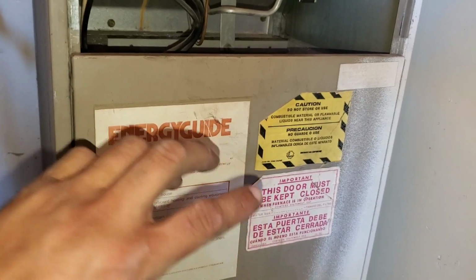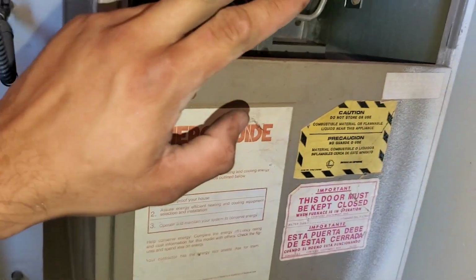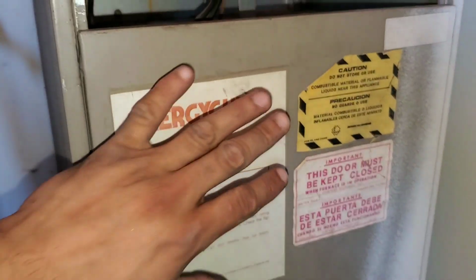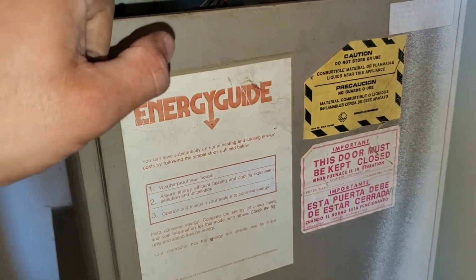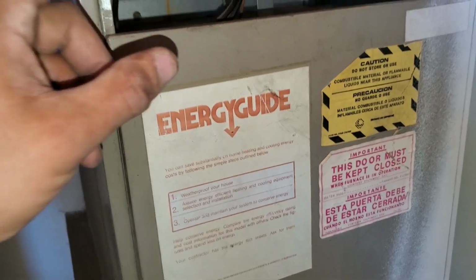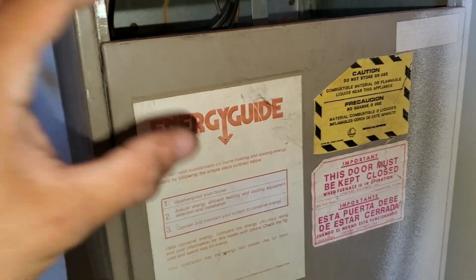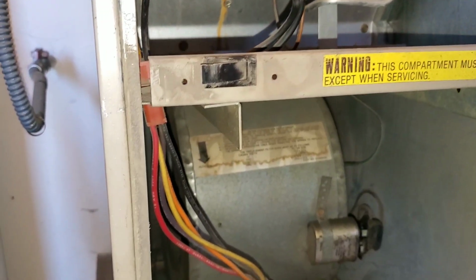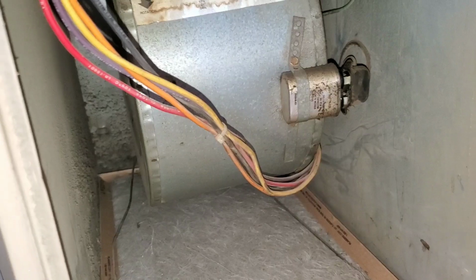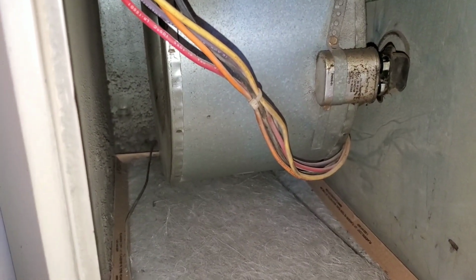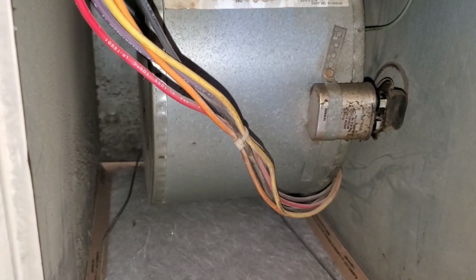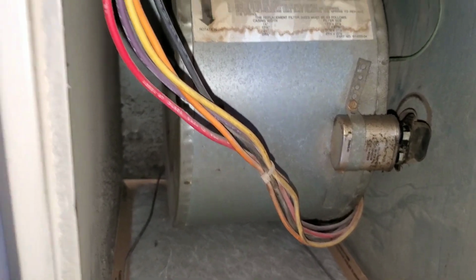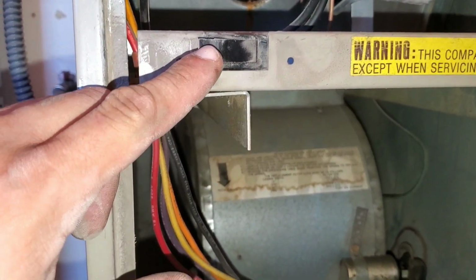Every system has a safety, either a door switch or some type of switch on the wall, like a light switch, so that you can remove power to your system. As soon as I remove my front panel, that will cause the safety switch, the door switch, to disengage, and that will remove power to my system. And you can see here, as soon as I remove my front panel, this is where my blower motor is. Right now we want to ensure that our blower motor is running. So I'm going to manually hold my door switch and then we're going to allow the blower motor to turn on.